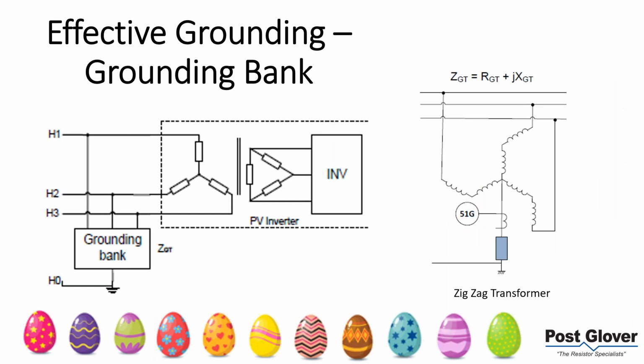I see this a lot in renewable applications. Usually it's a transformer. We get a lot of requests for zigzag transformers, which, by the way, just from a sales perspective, we don't actually provide by themselves. We provide those in packages. But the point is that the most common way to have what's called a grounding bank, there's a couple of different transformers you could use. You could use a Y-delta or a zigzag. I just put the zigzag here. It's more efficient to use a zigzag. We don't have enough time to go into how you size those, but if you look at the different ways you size them, you would find that a zigzag is a little more efficient. You're going to get a smaller zigzag for your buck.